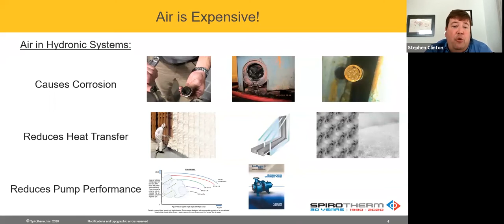Now most systems have used traditional tangential air separators - that's the Rolairtrol on the left, which has been around for decades. The current version, manufactured by different manufacturers, is basically just an empty vessel with nothing inside. The thing I noticed when I first went to the Little Red Schoolhouse for training early in my career was I wondered why we'd have a device that swirls water around, pushing it from the top down and taking it out the bottom, when the air bubbles are trying to rise to the top. That's something to consider, because those small bubbles don't have much buoyant force to counteract the direction of the water flow.